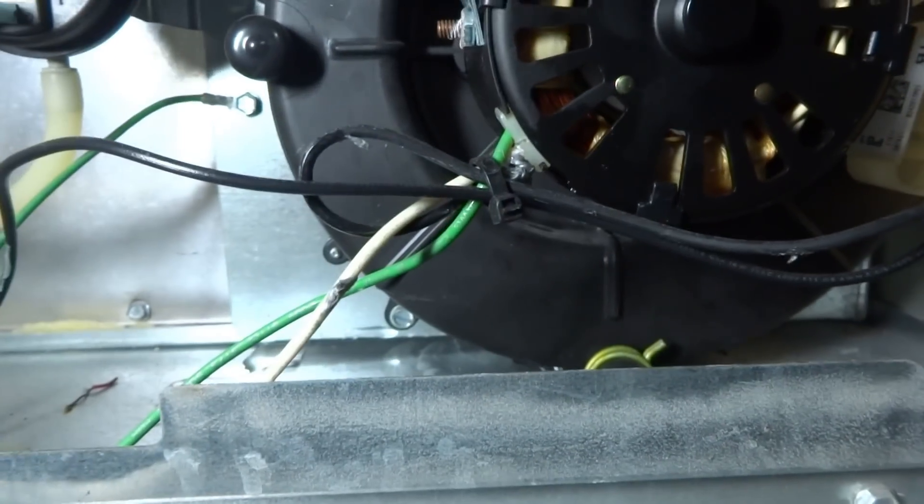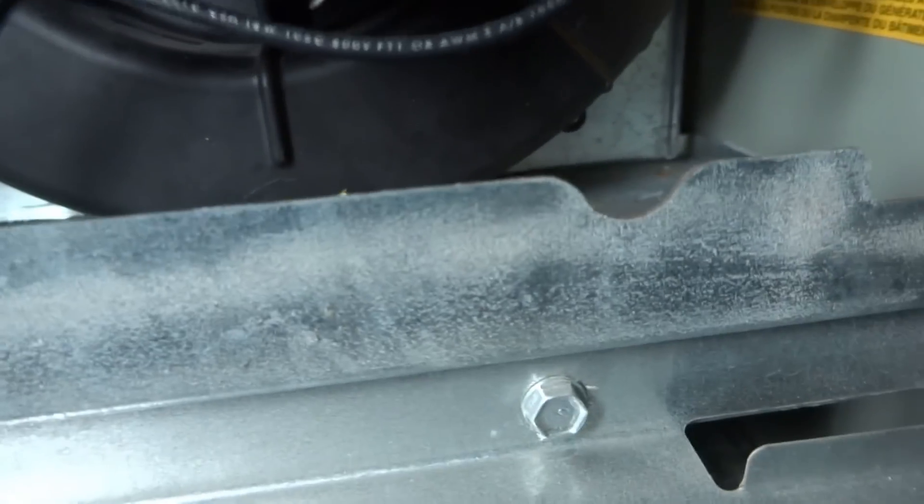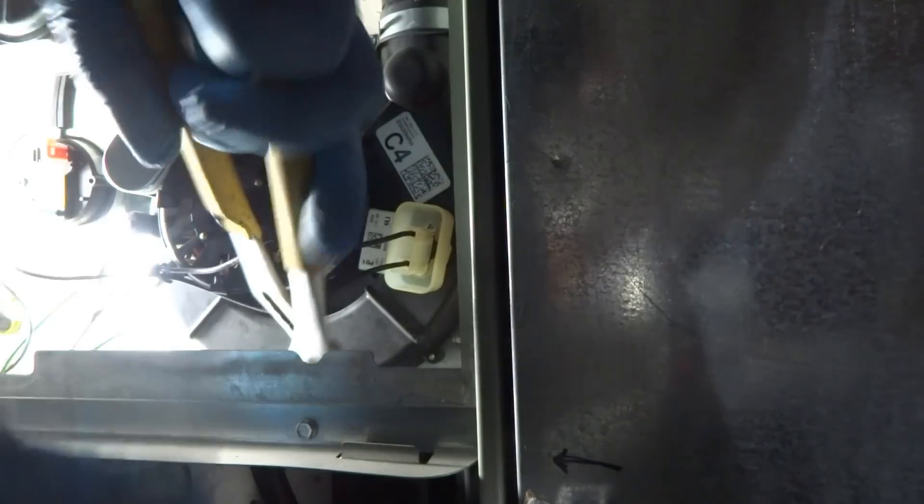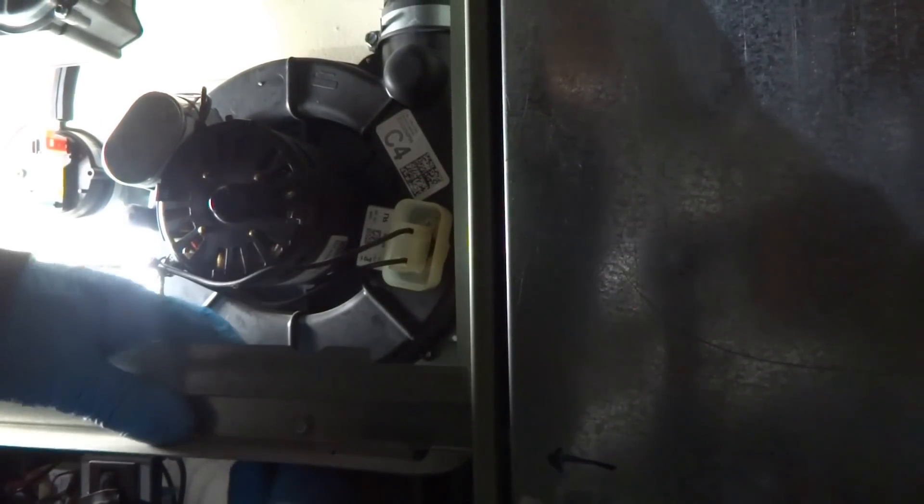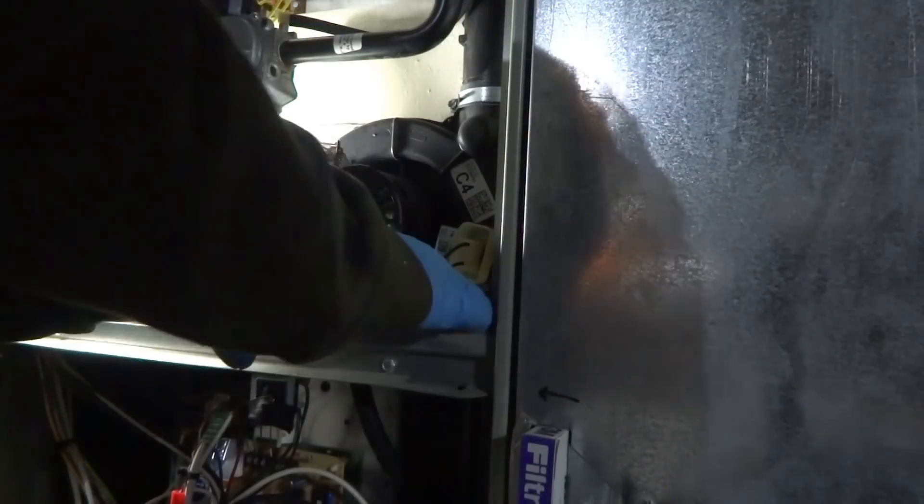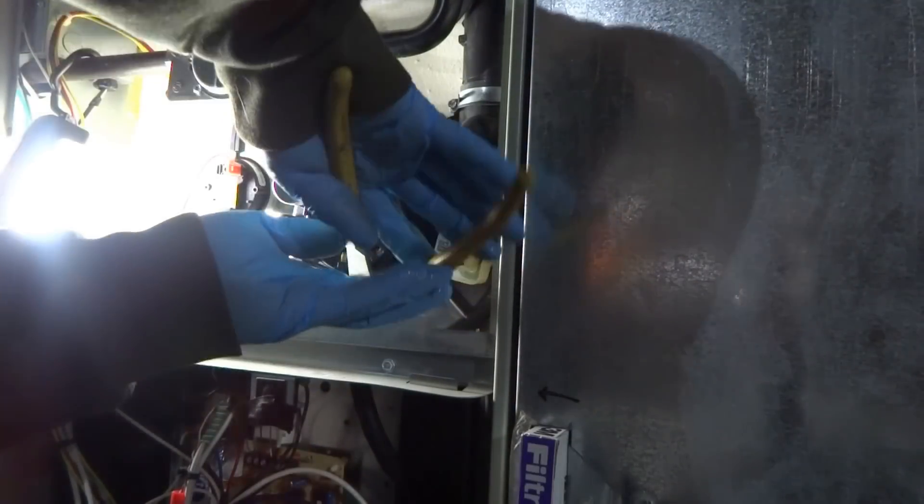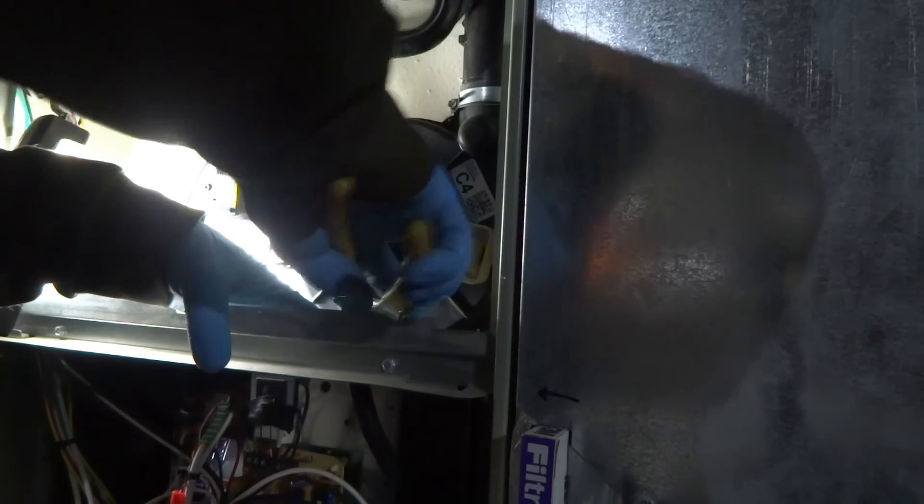There's a little water in there. Yeah, it doesn't sound like there's water in there or something. Maybe this drain is backing up. Let's check it out. Yeah, that thing's full of water. That thing's full of water, so this drain must be backing up. Yeah, but I didn't replace the... Maybe the drain's just backing up. Let me make sure that there's water in that pump, which shouldn't be, right? Let's see what we can do with that. The condensate might be backing up.